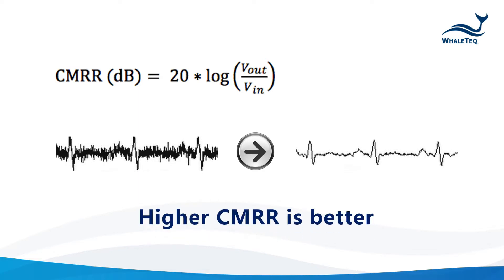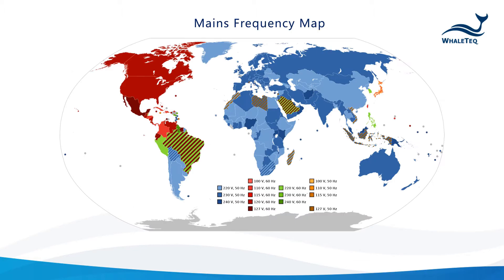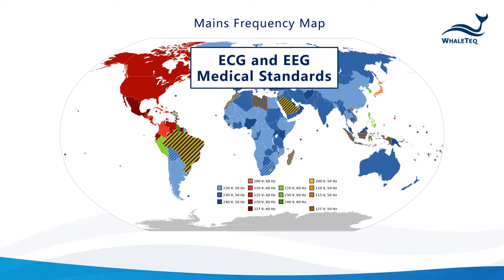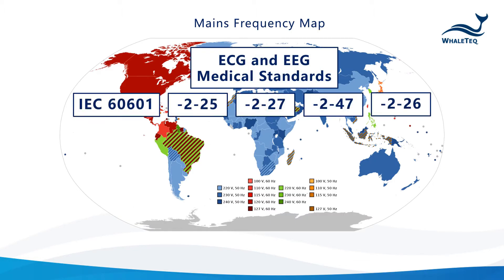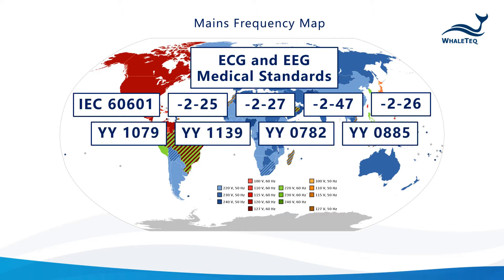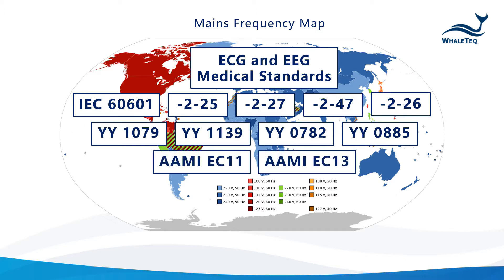A significant noise source comes from the electrical grid's mains frequencies. Standards like IEC 60601, YY1079, and AAMI EC11 require medical devices to exceed certain CMR values for their respective mains frequencies.